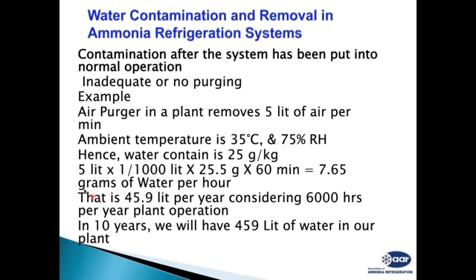Now, when we say 5 liters of air is being removed from the system continuously per minute, it means that 5 liters of air is being injected into the system continuously. So we are entering 7.65 grams of water per hour. You can see the calculation here: 5 liters times 60 minutes gives 7.65 grams of water per hour. That is 46 liters of water entering the system in 1 year of operation. In 10 years, we'll have around 460 to 470 liters of water just because of the air entering the system. This water is from the air. Even though your purger is removing the air, this water will remain.